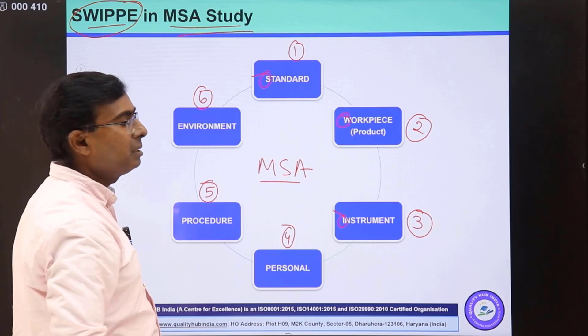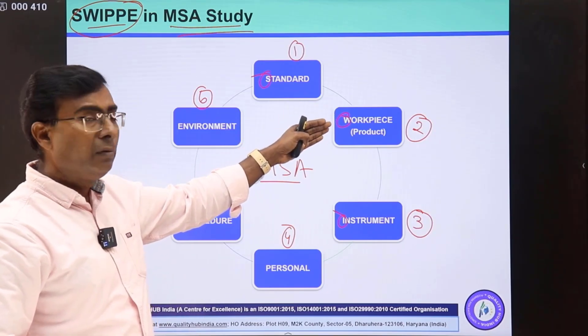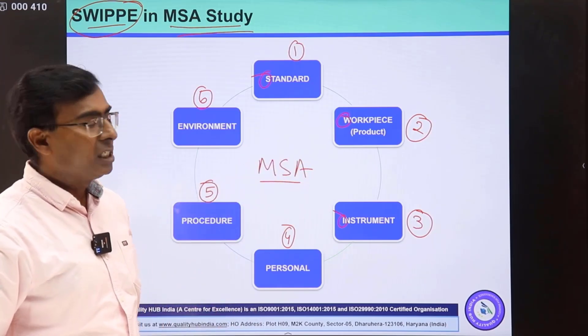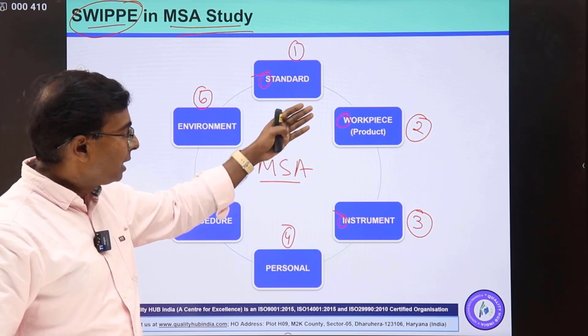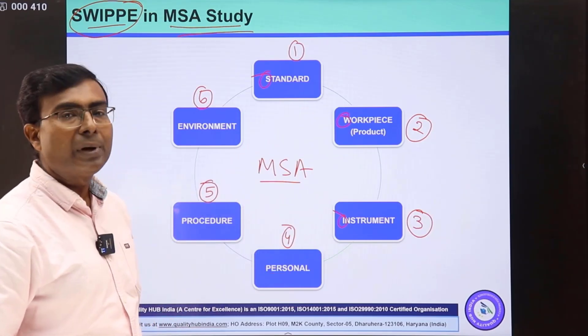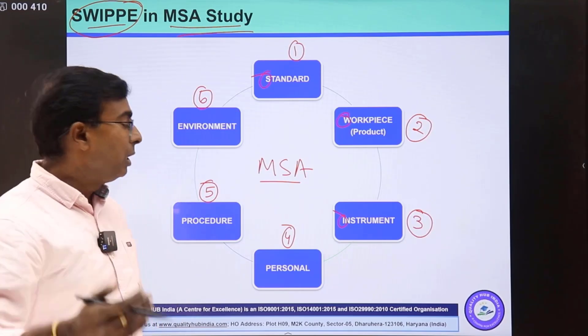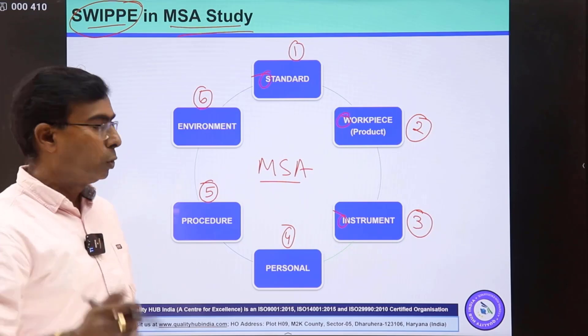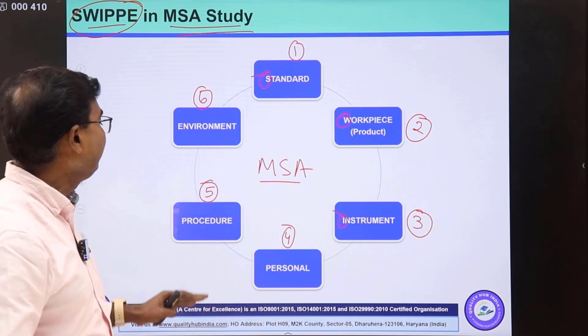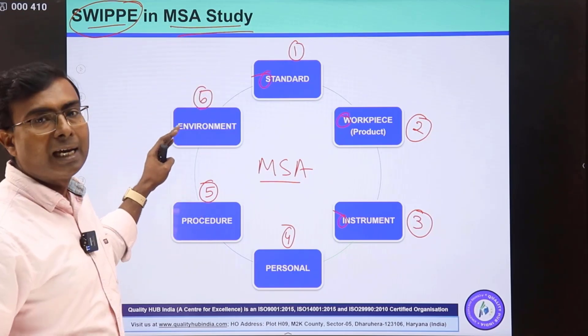We need to have some standard in place. We need to have some workpieces for our study — generally we take 10 pieces for variable study and 50 pieces for attribute study. Then we need to have some instrument or gauges for the study. We need to have some appraiser who would be inspecting, and in attribute study we need to have an additional expert also. Then we need to have some work instruction, procedure, or guideline for conducting the MSA study.